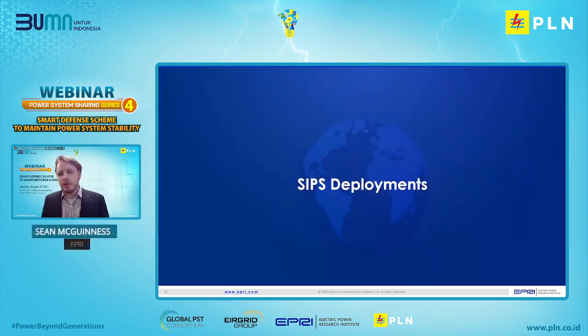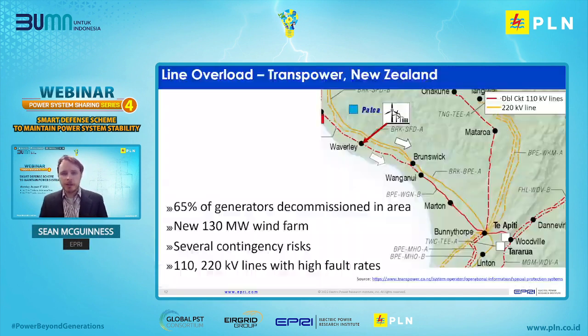So I want to give some examples of deployments around the world. The first one, on the next slide, is typical of what is probably the most common type of special protection scheme deployed around the world: overload-based schemes. These are very popular now where wind farms or solar PV farms are connecting into the grid, where there's a high risk of overloads occurring for certain grid conditions and scenarios.